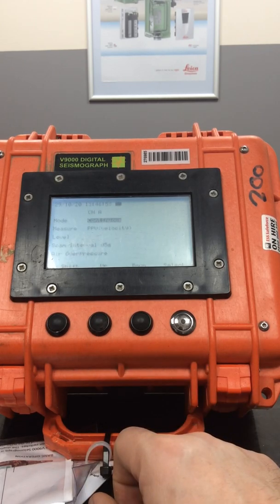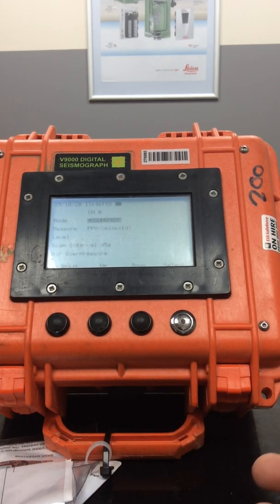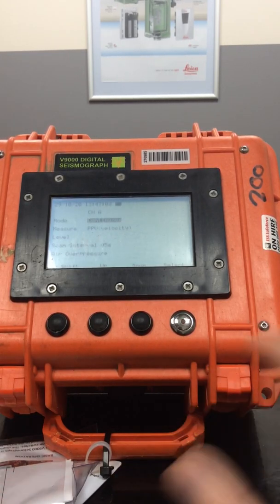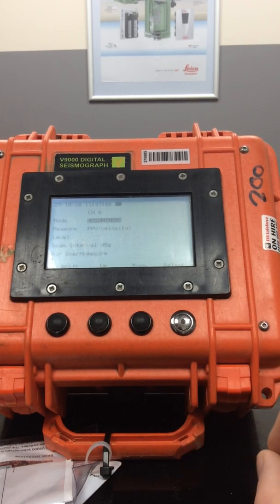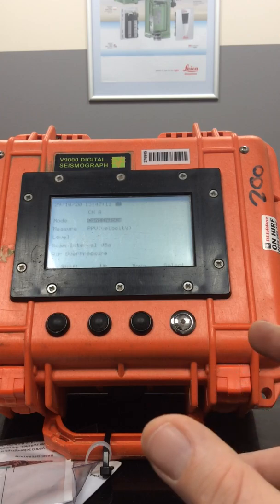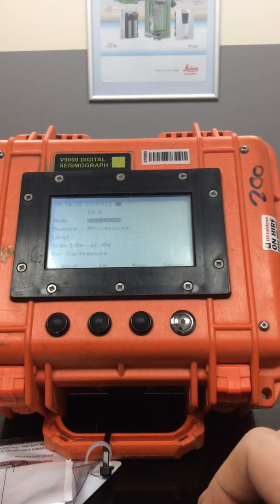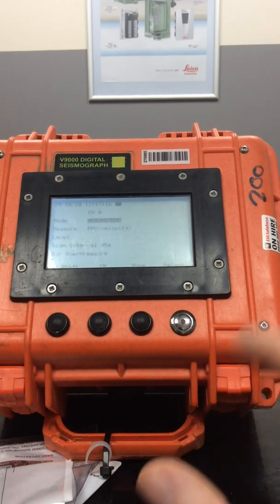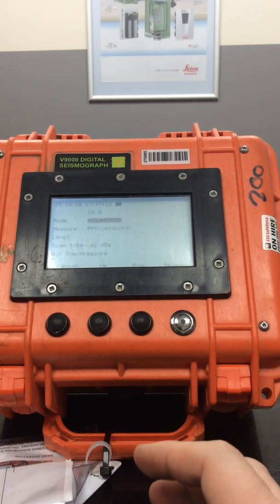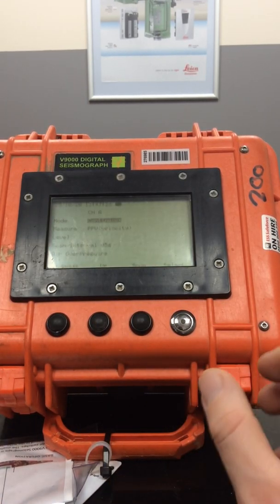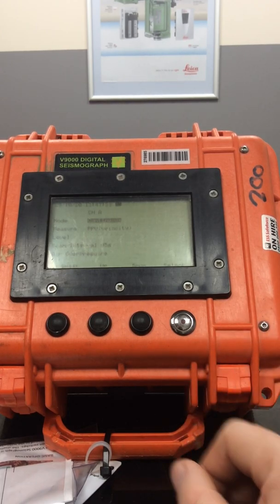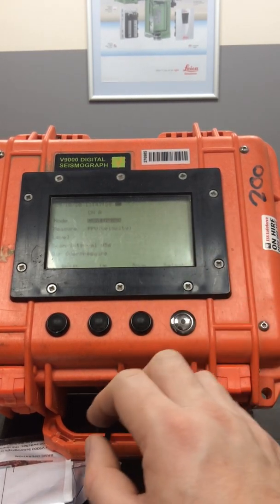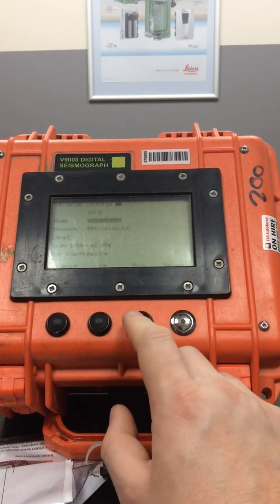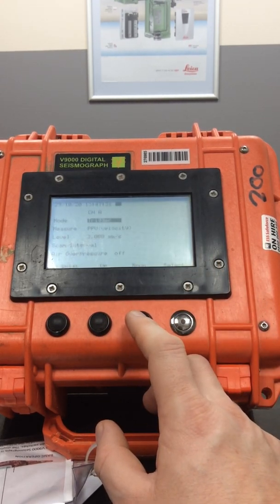I can do it continuous. If you leave it on continuous mode, it is going to record every single little bit of vibration throughout the time the machine is on. So that will ultimately fill up your memory on this instrument. I would highly recommend using trigger mode rather than continuous mode, because ideally you'll have a level you want to look at and you will need to record above that. You can have it in continuous, but it will swallow up your memory. Once we've looked at that, we can change it onto trigger mode.